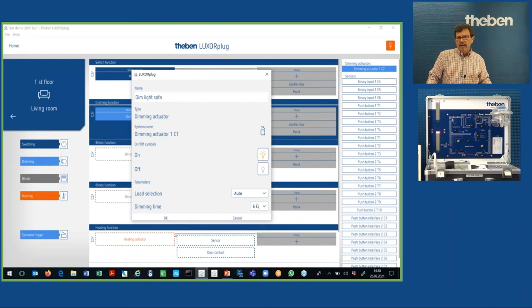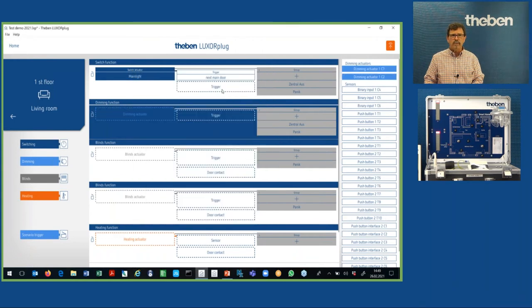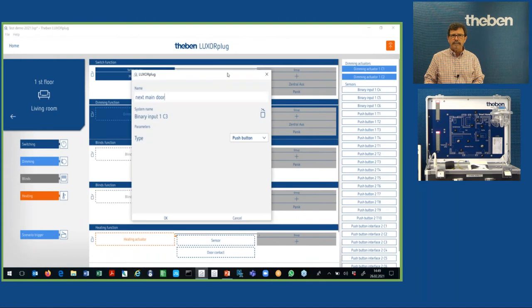Okay. Here you can adjust the dimming curves, especially for LEDs. And here you can adjust, for instance, the time from 0 to 100%. And this could sometimes be a troubleshooter in the event you have an LED which is rather fast from 0 to 100%. So it becomes difficult for you or for the end user to find, let's say, a dimmable value between 20 and 60 or 70% because the dimming curve is too fast. If you adjust it here to a longer time frame, okay, it was too fast, longer time frame, and you, sorry, what's the dimming?